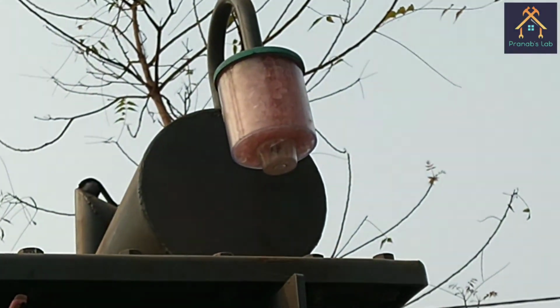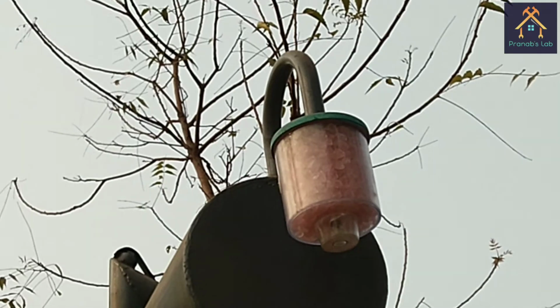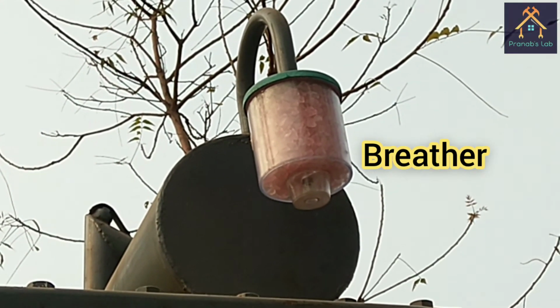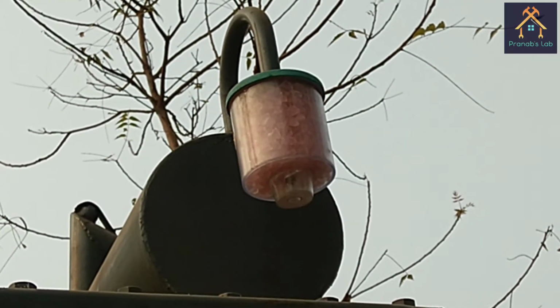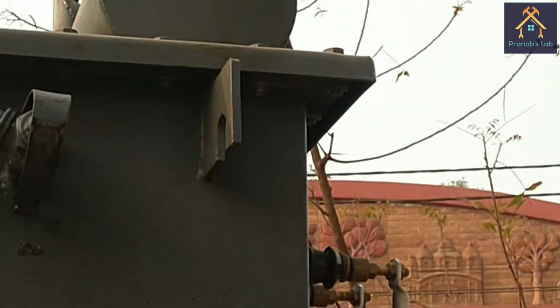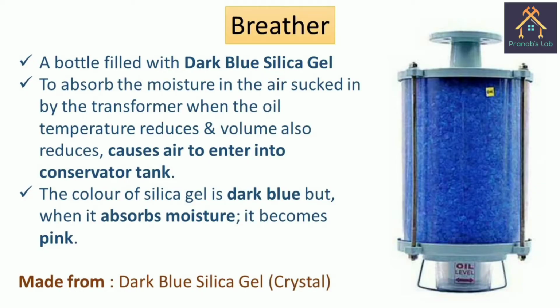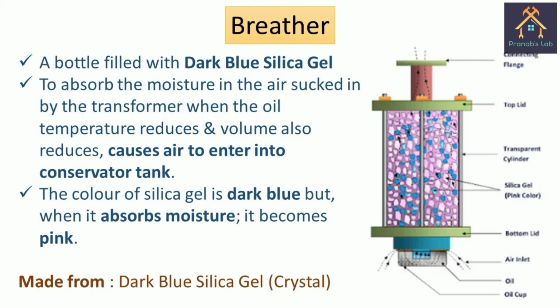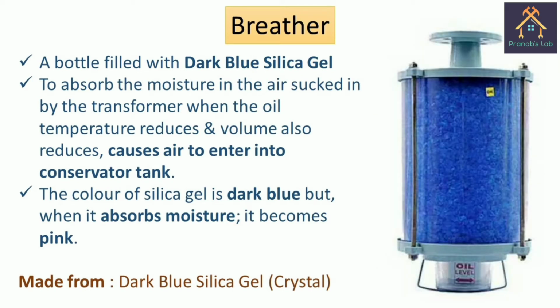Now you can see this is the breather of the transformer. Basically it acts as an indicator of the moisture content in transformer oil. Actually it is a transparent bottle filled with blue silica gel crystal. The main function of it is to absorb the moisture from air entering into the conservator tank. When the transformer cools down, then the volume of the oil reduces and draws air from the atmosphere. Then if the moisture with air enters into the tank, it will destroy the insulating property of the transformer oil.